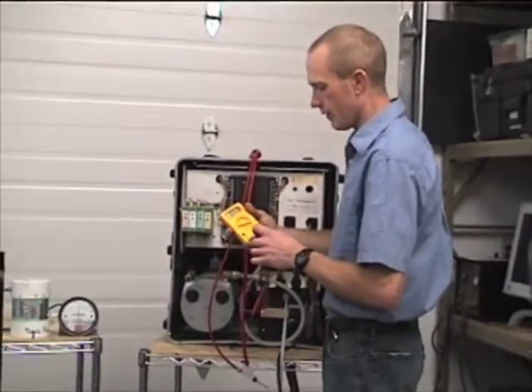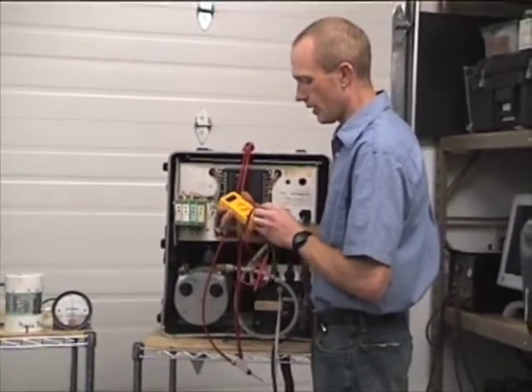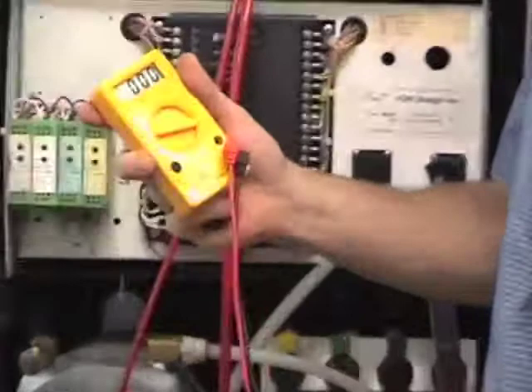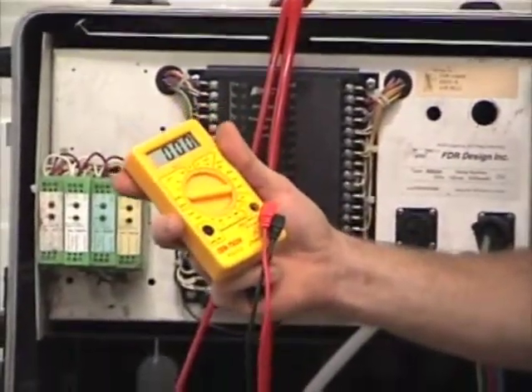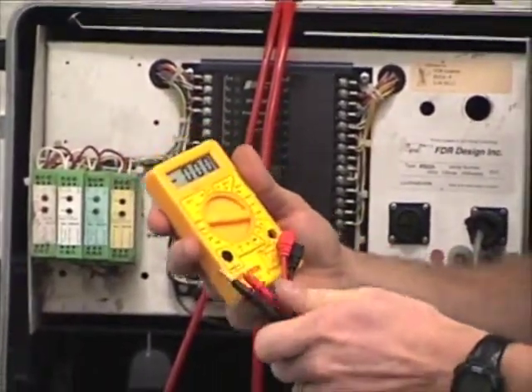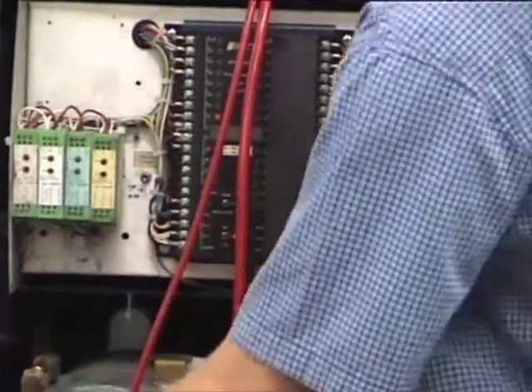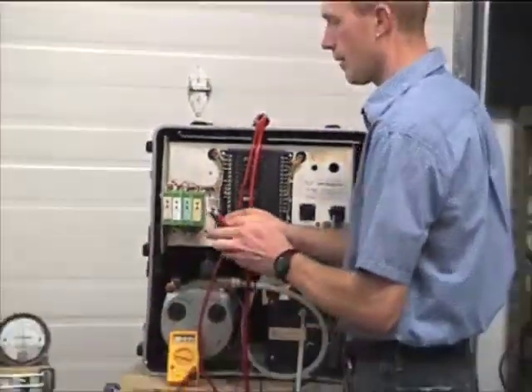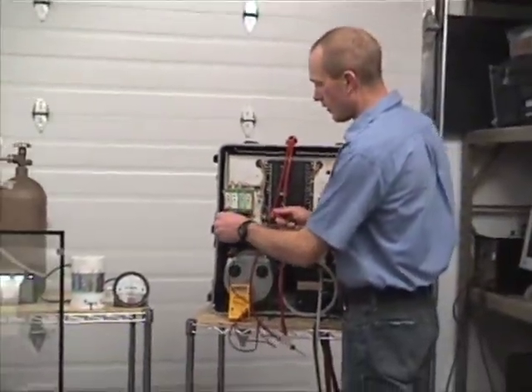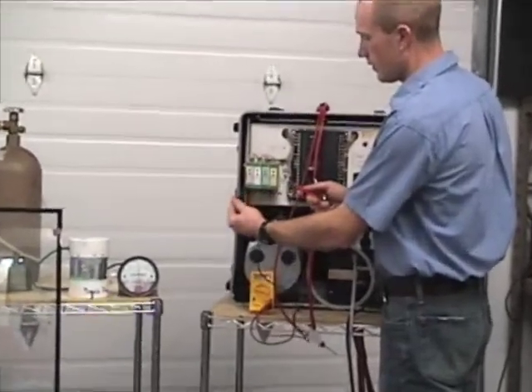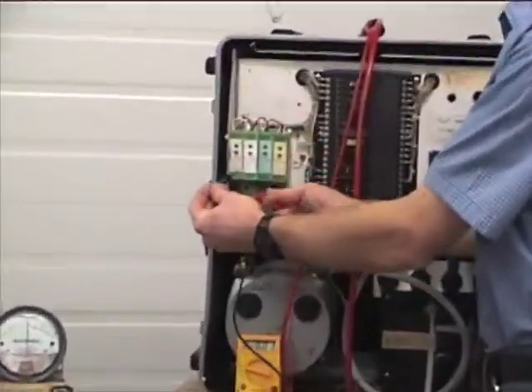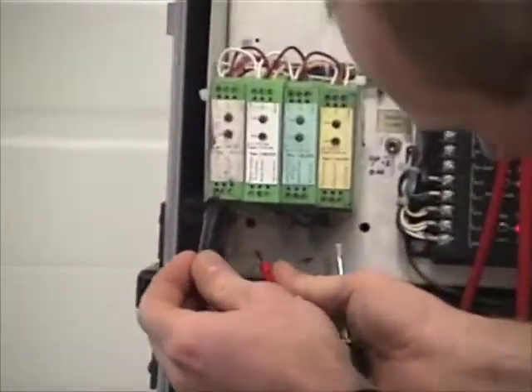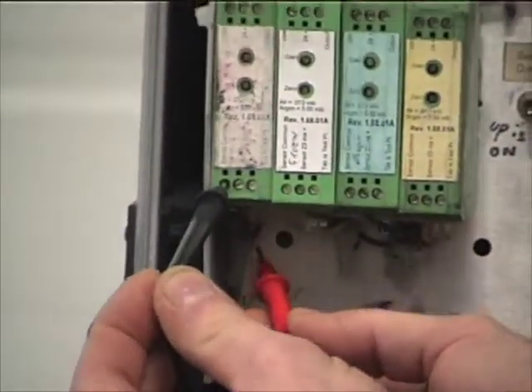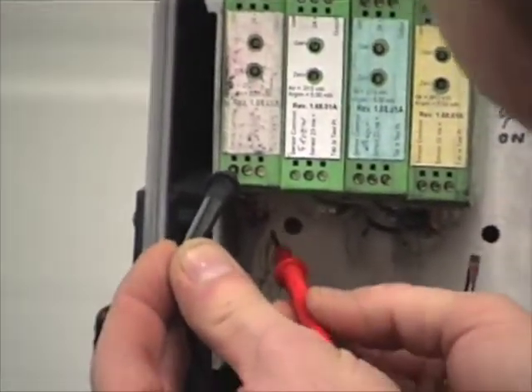If it's a voltmeter just like this one, you want to put it on 2000 M on the DC volt setting, and that's going to let us read millivolts. I'm going to take my black lead, and it'll go on sensor common, and my red lead will go on the test tab on the bottom of the amplifier board. You'll see there's a little metal test tab sticking down.